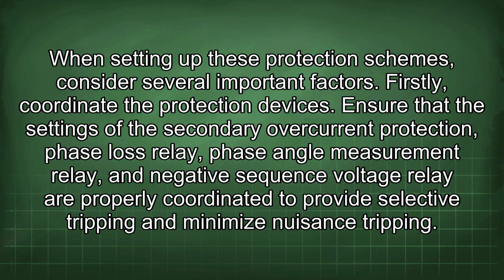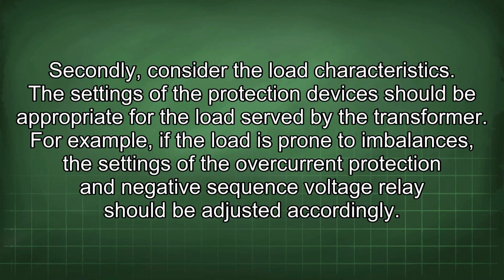Ensure that the settings of the secondary overcurrent protection, phase loss relay, phase angle measurement relay, and negative sequence voltage relay are properly coordinated to provide selective tripping and minimize nuisance tripping. Secondly, consider the load characteristics. The settings of the protection devices should be appropriate for the load served by the transformer.